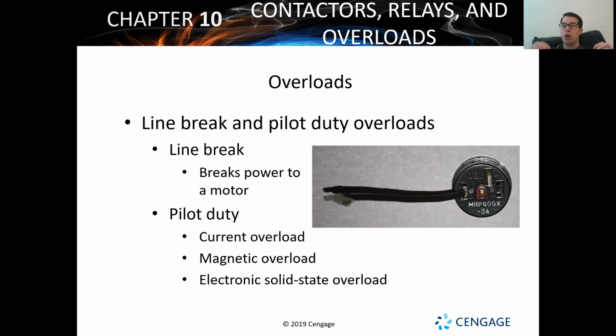If we have it where it's drawing in so much power that that coil is creating a greater magnetic field than what is required, then we're going to be shutting the system down. Now, the cool thing about the magnetic overload is it's related to the current relay or the current overload. Because how would a coil generate a greater magnetic field without introducing more amperage, introducing more electricity at one time? That's going to increase the size of that field. As that field increases, it disconnects the power and shuts down the system.